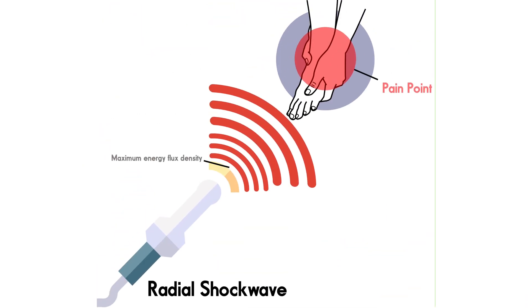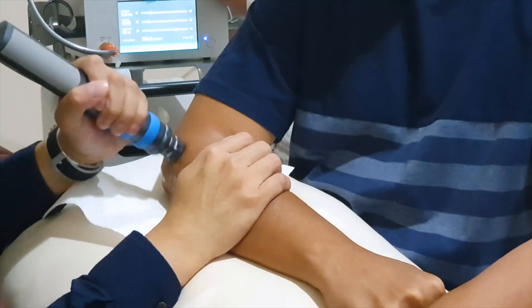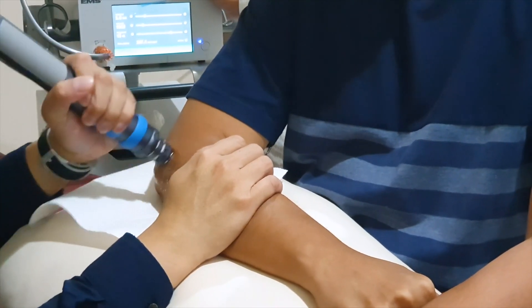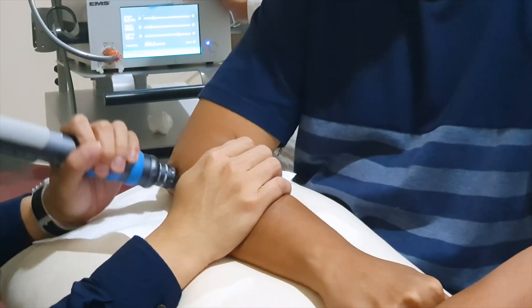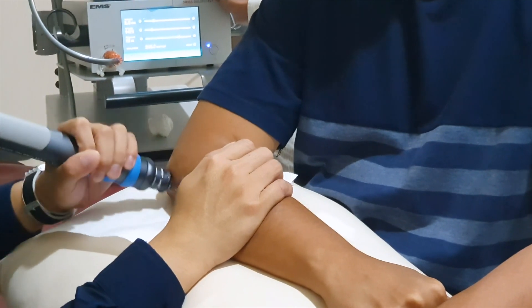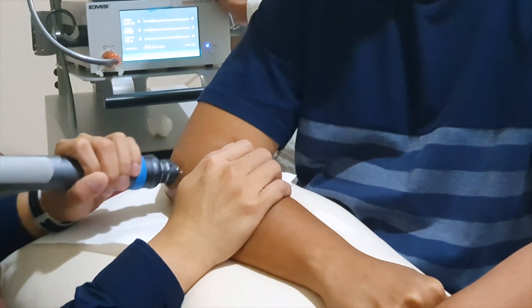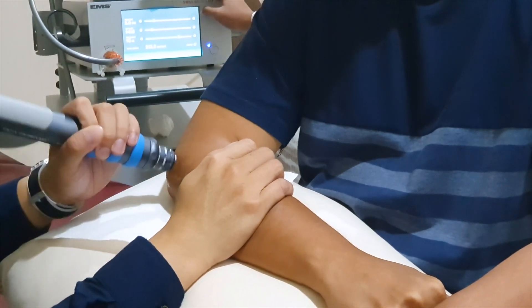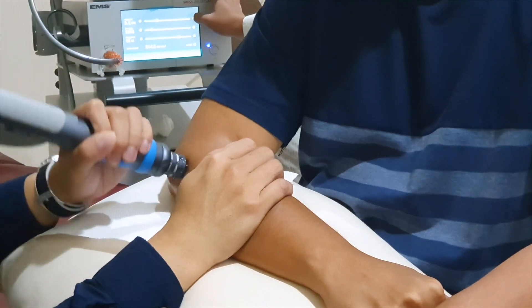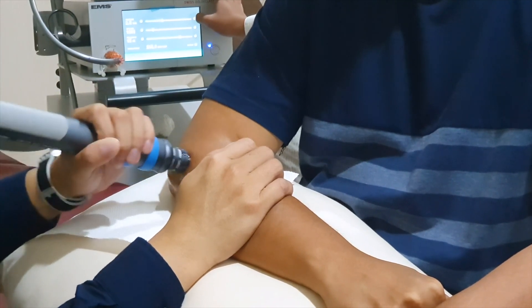In contrast, radial shockwave therapy's impact is more superficial, spreading out from the point of application. Radial shockwaves are not generated in water. They are generated using compressed air to accelerate a projectile into the applicator head, which itself creates a pressure wave that is then transmitted from the applicator head into the body.